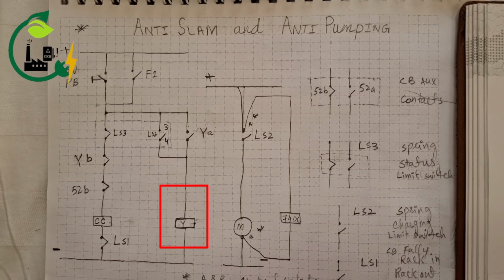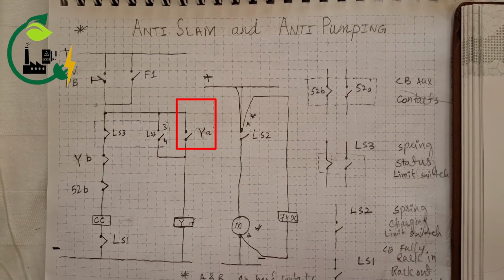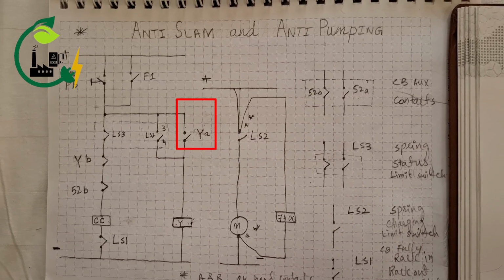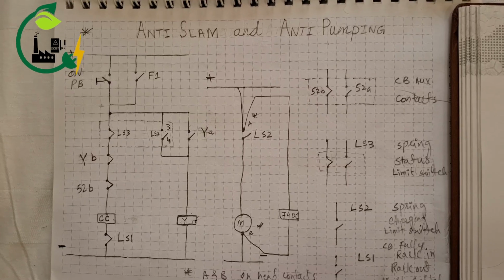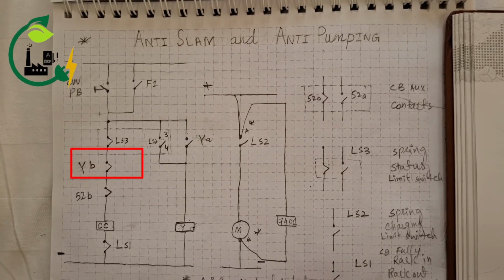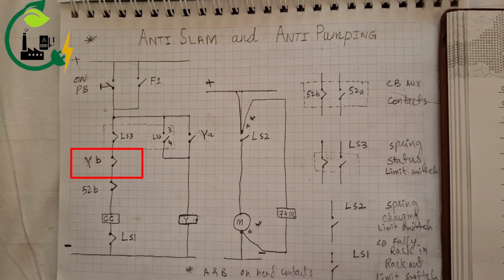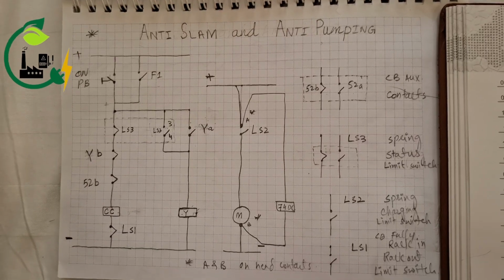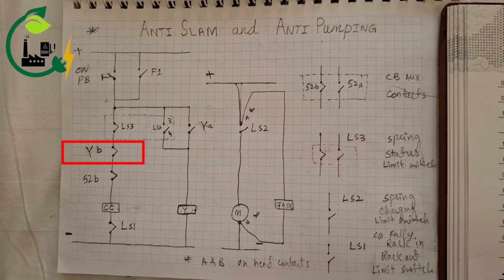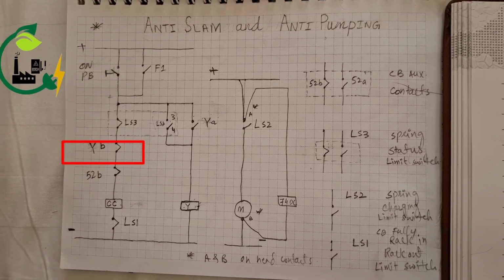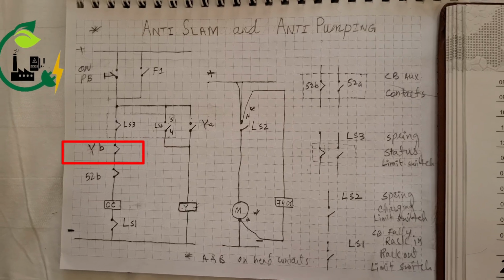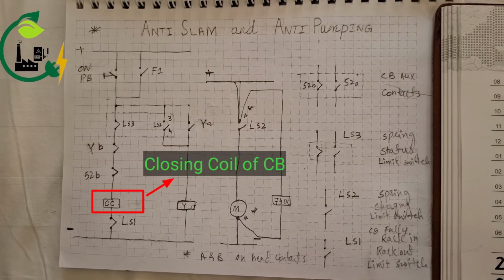For holding, we use the YA contact of the anti-pumping relay. The relay will hold, and we put the YB normally closed contact of the anti-pumping relay in the closing circuit. So once the anti-pumping relay is activated, it will cut the supply to the closing coil in any tripping case, and this will protect our closing coil.